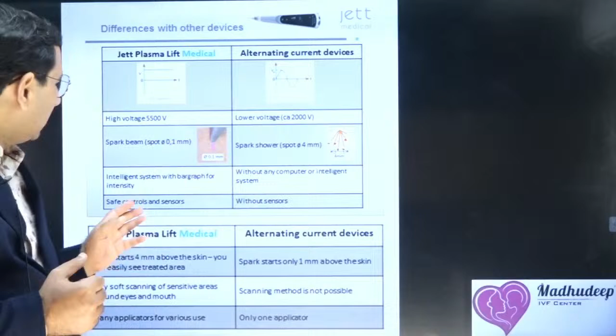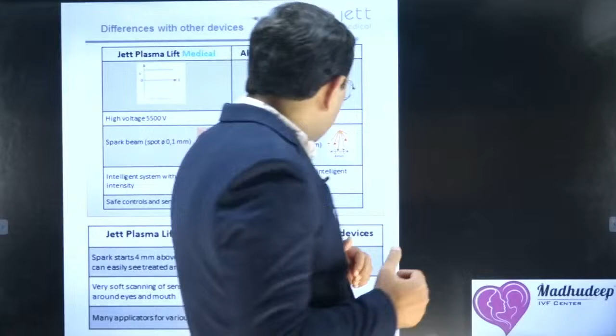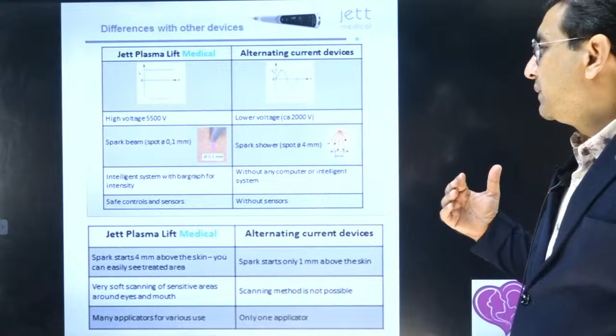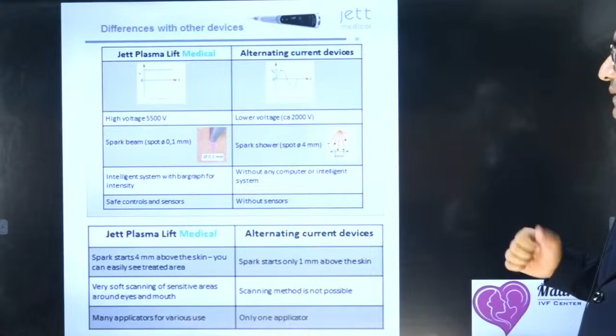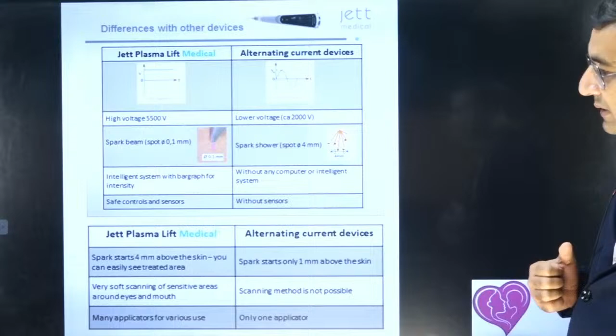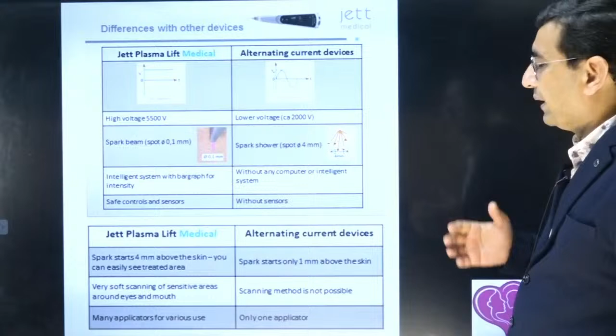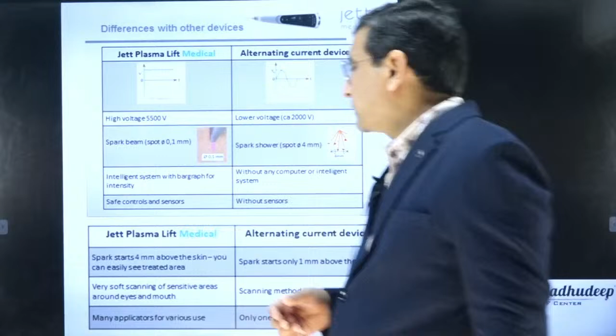Now, let us see, when we use a DC device, sparks start at 4 mm above the skin. You can easily see the treated area, whereas with the AC plasma device the spark starts only 1 millimeter above the skin. In the DC device, very soft scanning of the sensitive areas around the eye and mouth is also possible. The scanning method is not possible in the case of the AC plasma device. In the DC device, many different types of applicators are available, whereas in the case of the AC plasma device only one type of plasma applicator is available.